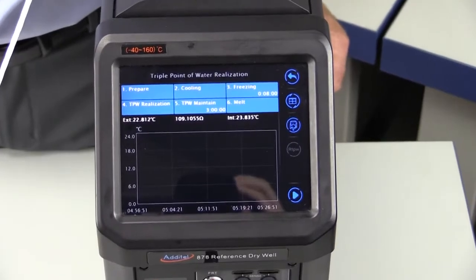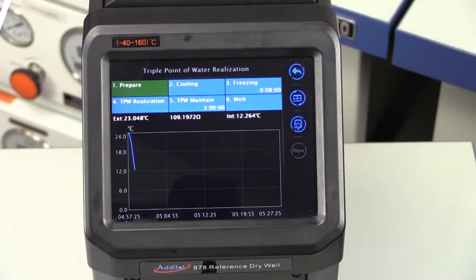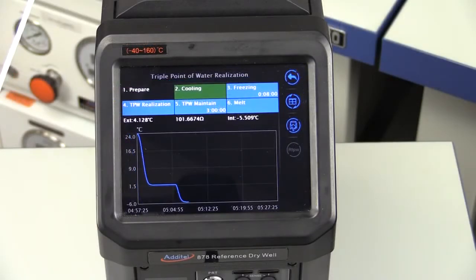The ADT878 will run down to 2 degrees C for 5 minutes to allow for some stabilization. By having the reference thermometer in the cell during the temperature descent, this will help to cool the reference thermometer, which will lengthen the triple point of water's plateau. The 878 will cool to about minus 5.5 degrees C to supercool the triple point of water cell. The reference thermometer being tested should remain inside the cell during this process.